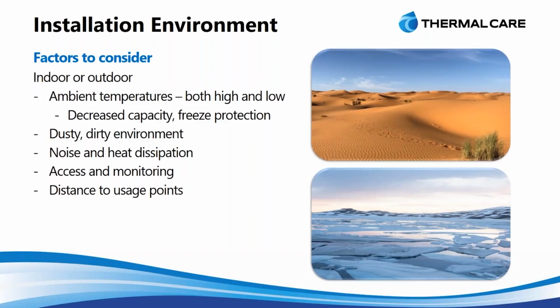The first is the ambient conditions. Are you in Phoenix or are you in Chicago? You're going to experience different ambient temperature ranges, so you want to protect on both the high side and the low side. In very hot conditions, as we talked about with the increase in ambient affecting capacity, we want to make sure our unit can handle the heat but still meet the cooling demands of the system.